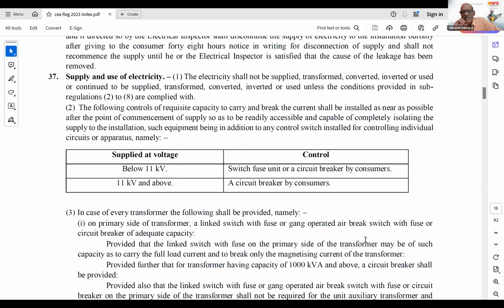Yes, sir, the point is whether multiple breakers, this is somewhat different. Whether we require a breaker at all at the point of supply. Another thing, we require one more breaker. I accept your view. The provision of further breakers in series in a circuit is quite unnecessary, and the regulation doesn't demand that. What the regulation provides is a strict liability of providing a circuit breaker at the point of supply.